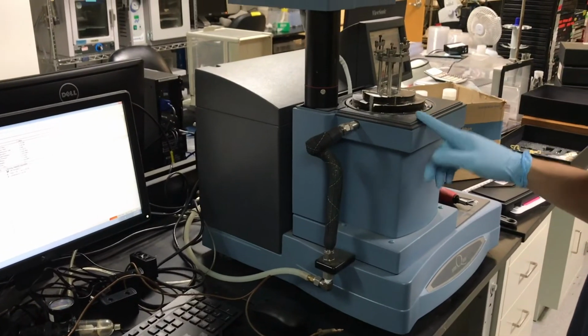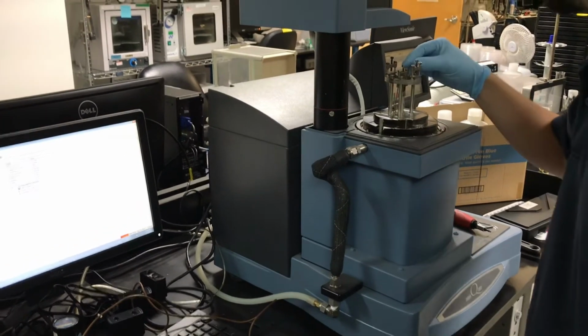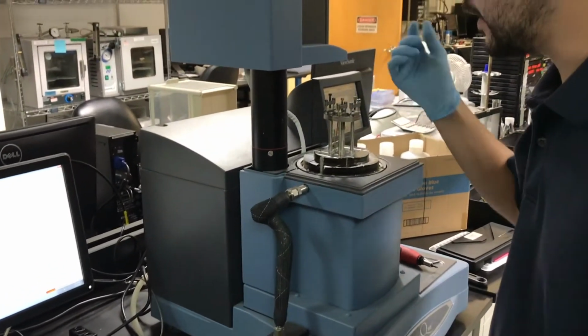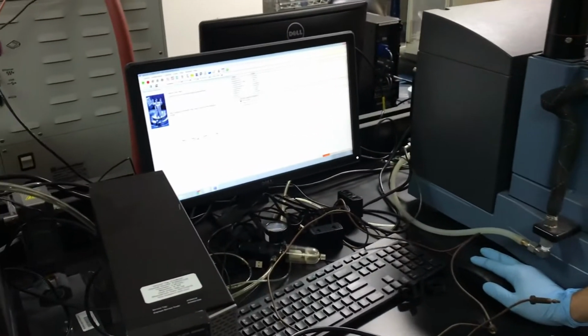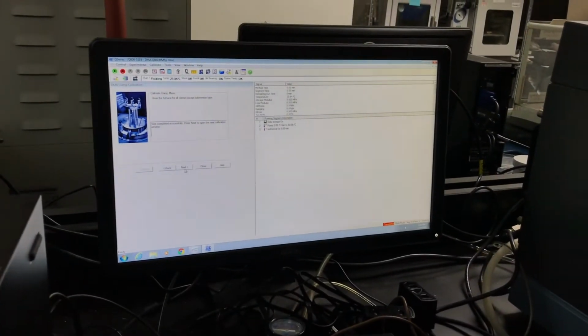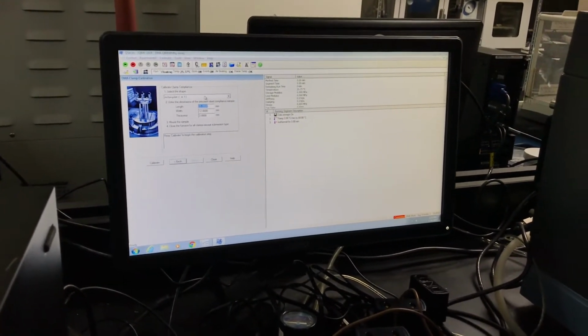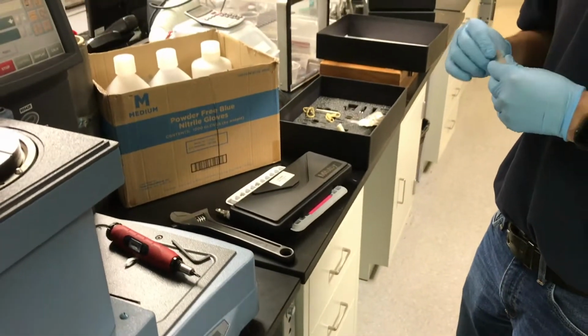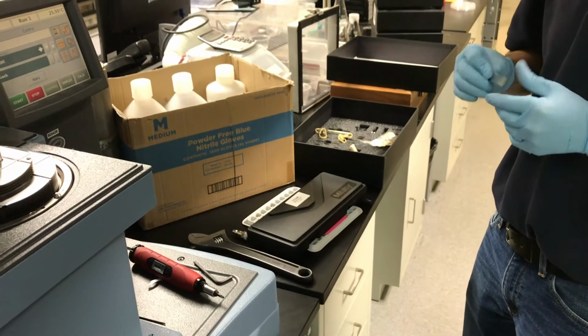Part of the calibration is complete, basically the mass calibration of this center clamp right here. So we can move on to the next step. Step completed successfully, press next to open the next calibration window, next. Then it wants us to use one of the calibration standards. And that guy is this one right here. There's a bunch of other ones, but this is for the dual cantilever.